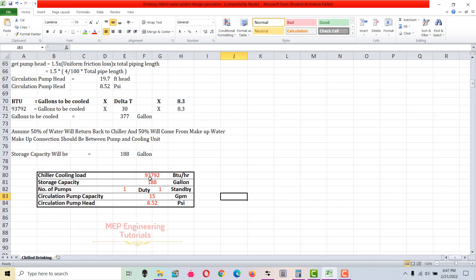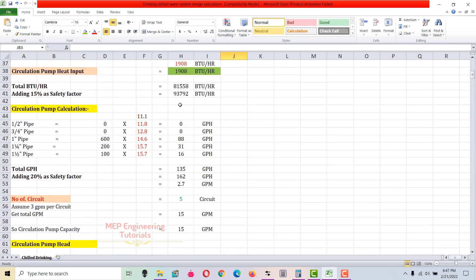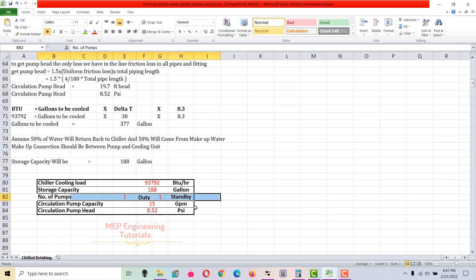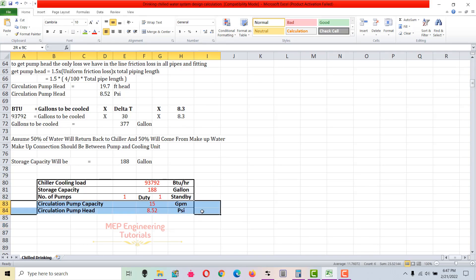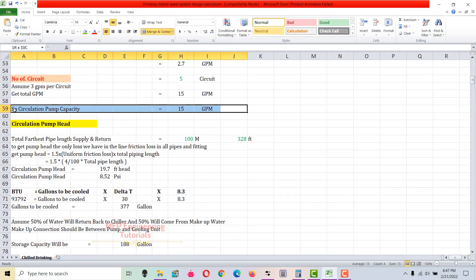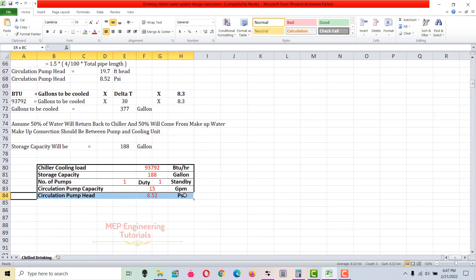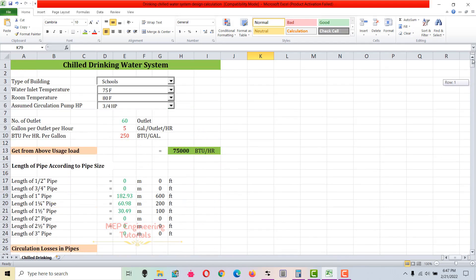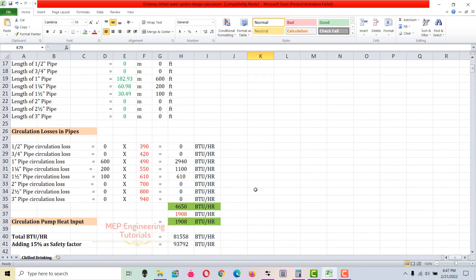To summarize all results: chiller cooling load is 93,792 BTUs per hour; storage capacity is 188 gallons based on 50% water return; number of pumps is two — one duty and one standby; circulation pump capacity is 15 GPM based on 3 GPM per circuit; and circulation pump head is 8.52 PSI. This is how you do the calculation for a chilled drinking water system. I hope you learned something — keep watching and don't forget to subscribe. Thank you.